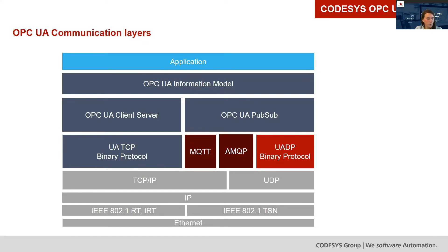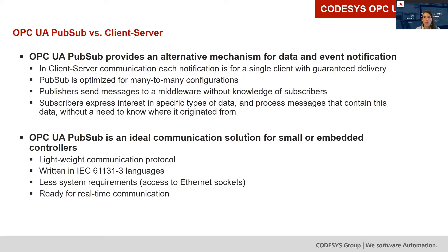OPC UA PubSub provides an alternative mechanism for data and event notification. In comparison to client-server, which is communication with single clients with guaranteed delivery, PubSub is meant for many-to-many configurations. A PubSub publisher sends a message to a middleware without knowledge of any subscriber, and the subscribers express their interest in specific types of data and process messages that contain this data, without the need to know where it originated from.